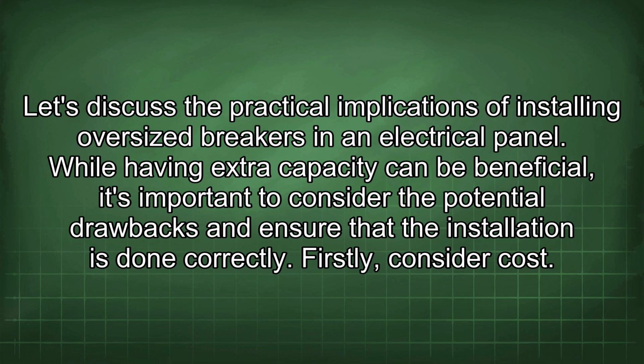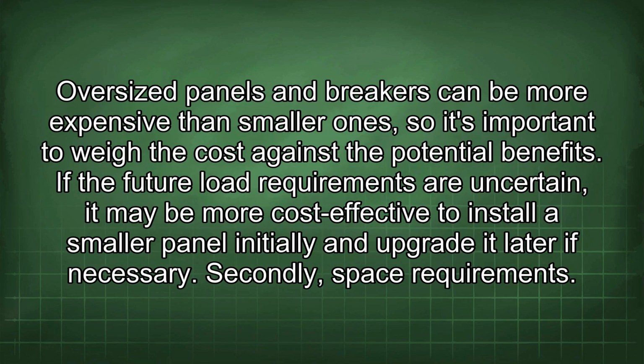While having extra capacity can be beneficial, it's important to consider the potential drawbacks and ensure that the installation is done correctly. Firstly, consider cost. Oversized panels and breakers can be more expensive than smaller ones, so it's important to weigh the cost against the potential benefits. If the future load requirements are uncertain, it may be more cost-effective to install a smaller panel initially and upgrade it later if necessary.